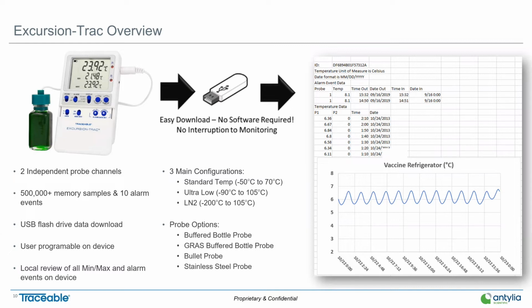And then within the offering, we have 4 probe options. Pictured here is our buffered bottle probe. That bottle is glass and it's filled with a glycol mixture that is GRAS, generally recognized as safe by the FDA. We also have a GRAS specific buffered bottle probe that's made of plastic. When you drop those glass bottle probes, they will shatter. So a plastic bottle probe is available as well. We sell the unit with just a bullet probe with no buffer on it. And then we sell stainless steel probes. And the ultra low and liquid nitrogen applications only come with the stainless steel probe. Obviously our plastic would freeze and break if we let it get that low on our bullet probes.